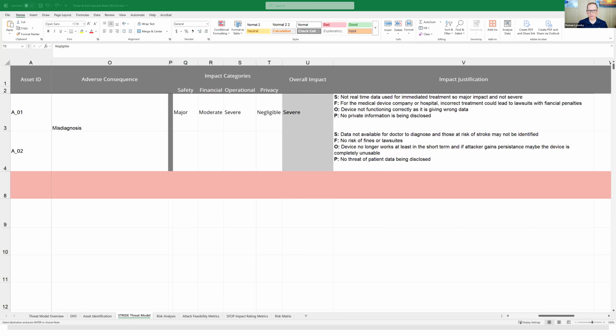And for privacy, there is a potential connection depending upon what information is disclosed, as the private PHI data that is disclosed could have an impact on somebody's ability to get insurance. So there is a connection there, and it'll depend upon the hazard analysis that you're doing. So I think it's always important to consider all of these categories and have a holistic view around it, and then tie it all back to safety as part of the final submission to the FDA, because that's ultimately what they're going to be looking at.